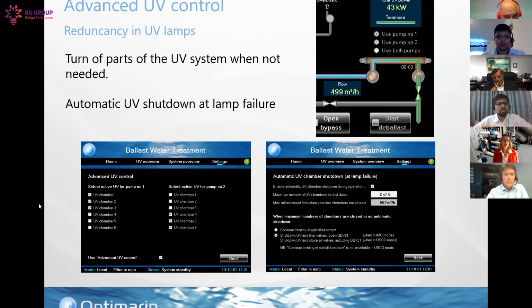Then there's advanced UV control. So if you have a very large system, for example a 2000 cubic meter per hour system with 12 lamps, 12 tubes, you can say, okay, now I'm running only one pump, so I only want to use these 3 lamps plus these 3 lamps, for example. That way you can choose to use part of your system instead of the entire system when that's applicable.